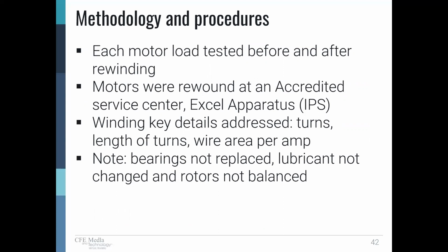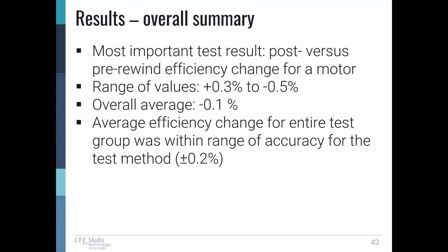And the key details of the winding that were addressed: turns, length of turns, wire area per amp. The factors that could change things like winding resistance or winding magnetic turns could change the core losses by changing the magnetic strength. Also, bearings. We were trying to focus on changes affected by rewinding work. So bearings weren't replaced, lubricant wasn't changed. The bearings were wrapped, the end brackets were wrapped, the rotors themselves were wrapped, everything was wrapped up and stored while the winding work was done, so nothing was disturbed. The rotors weren't even balanced. We didn't want to change anything there. We don't want to introduce anything that would make a change other than the windings and the cores.